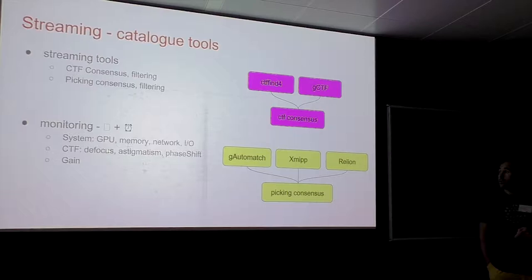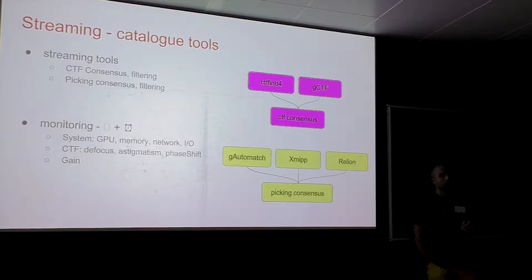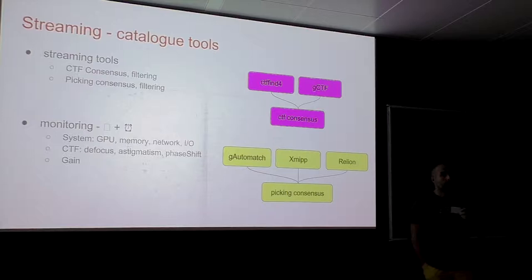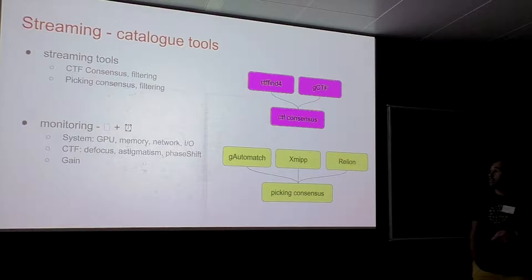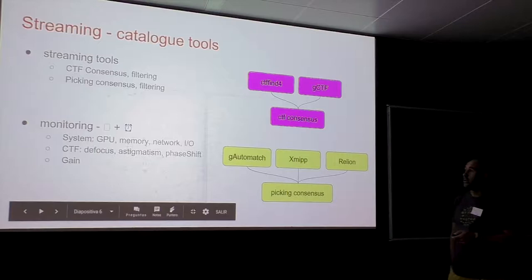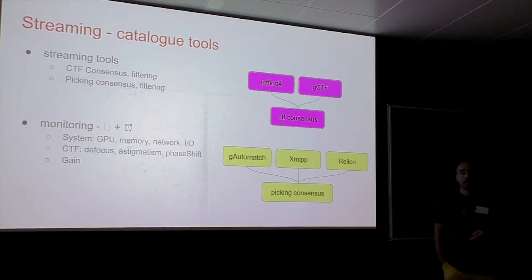You can also monitor the gain — this comes from an XMIPP method that estimates the gain from a micrograph, so you can monitor whether the gain has changed during acquisition, checking every 500 or 1,000 movies. You can also get a report summary of the acquisition as an HTML file — a self-contained folder you can access anywhere on the network. It summarizes basic acquisition information, lists the methods used in the workflow, and includes CTF monitoring charts for resolution and focus coverage.